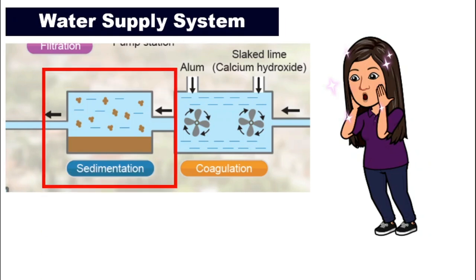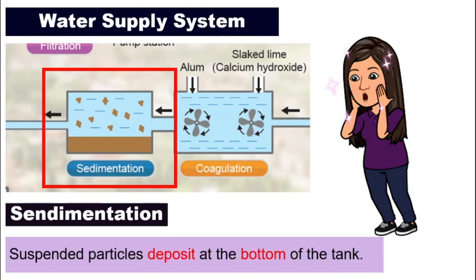After that, the water will be channeled to the sedimentation tank. The water will sit here for a while. Remember, in our coagulation tank we added alum, which acts like super glue for the mud particles to stick together and form bigger ones. So in the sedimentation tank, these particles will deposit — they will have time to sink to the bottom of the tank. We will then drain out all the suspended particles that have been deposited at the bottom, so the water up here will be clearer and cleaner.